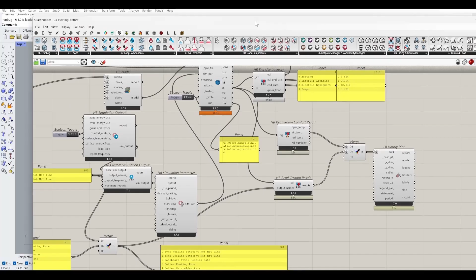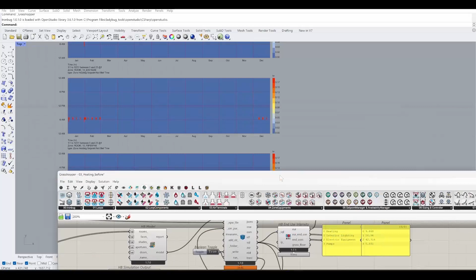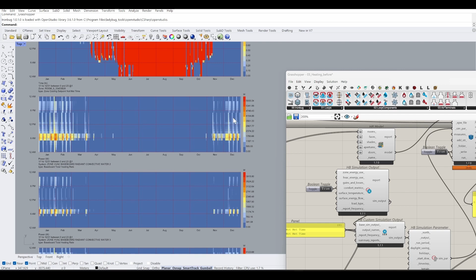Now let's look at the output result. So unmet hours are all fine. We have checked. This is a cooling unmet hour, and it's fine because we don't have a cooling system. This one is the baseboard total heating rate for each zone. You can see for this first zone, at the peak hour, it uses close to 6 kilowatt, probably here.